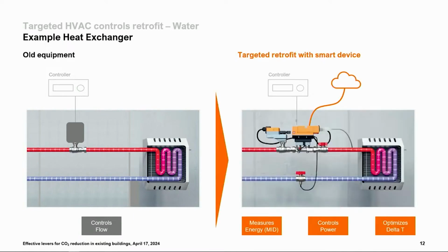So we have a kind of simple package. We, and also our competitors, have similar ones that allow you to upgrade a system with a very targeted measure. Rip out the old valve, put in the new one, connect it to the existing controller. Now you measure the thermal flow through this heat exchanger. You control the power, not the flow - the power. How many kilowatts are going into this heat exchanger?